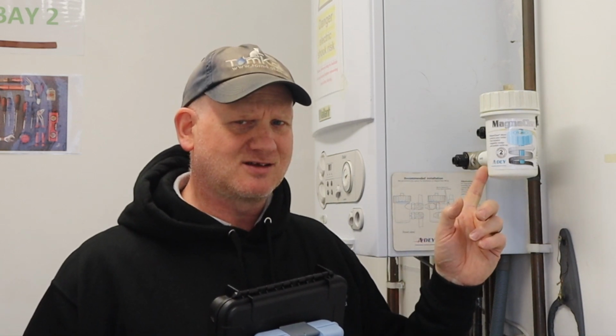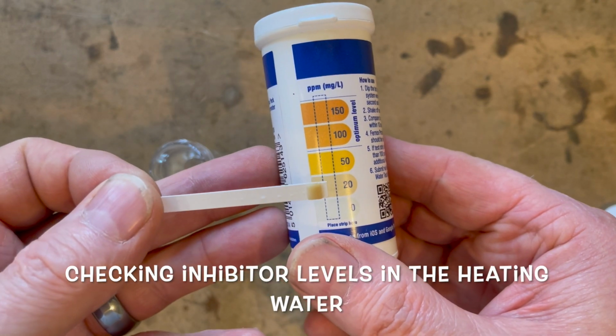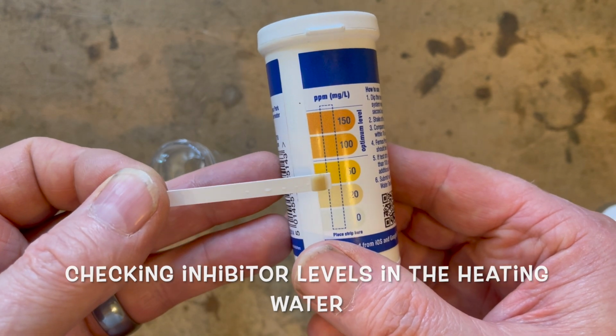And if your water quality is great, then technically do you need a filter? So every service now, your engineer should be checking the water quality of your central heating system, and also if you have a filter, they should be actually cleaning that as well. So when you're asking an engineer how much does it cost for a service, ask them first what is actually involved in my service, because you could see a service at 50 quid where they just put the flue gas analyzer in, or you could see a full service of 120, 130 quid where they're checking everything for you and giving you that extra peace of mind.